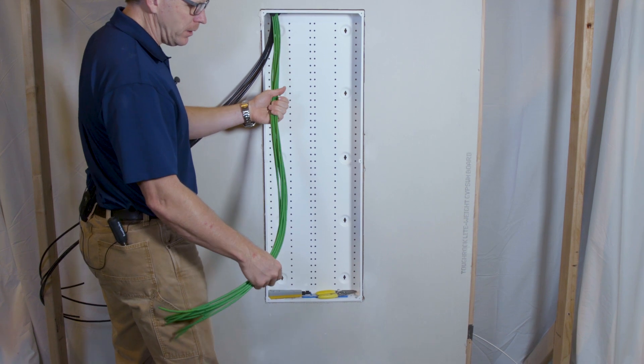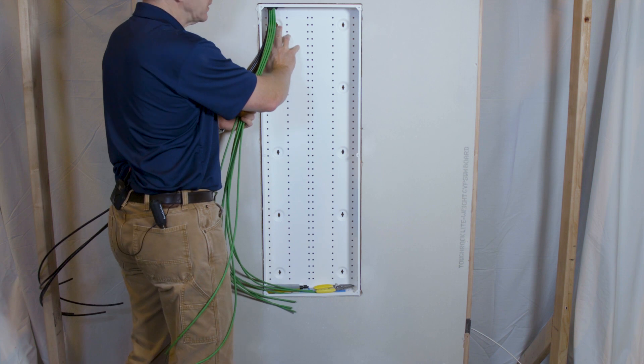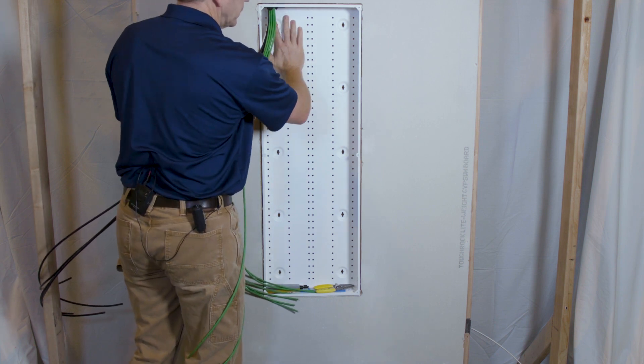Typically a good place to put this, because of the cable bulk here, is to put the terminating equipment as high up in the enclosure and as close to the entrance as possible. So we're going to put the twist and mount right here.